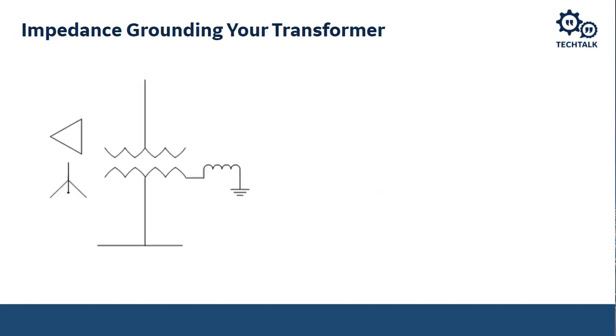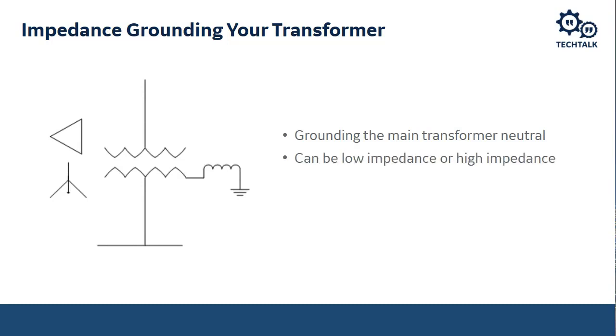The other method is to put an impedance to ground in our transformer. So we're grounding the main transformer neutral. Again, just like the grounding transformer, it can be low impedance or high impedance, depending on how we want to protect the system. And in the UK, they use resonant grounding, or Petersen coils, just for information. It's not used much here in North America. I do see it in a couple of installations, but we will not talk about or focus on this type of grounding.